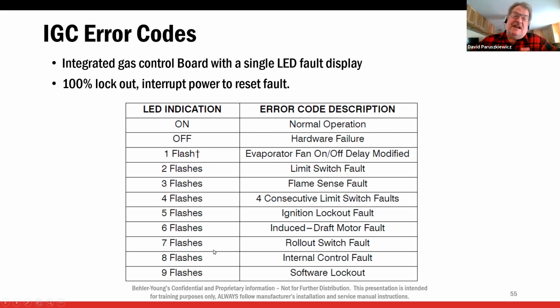So there are fault codes on the IGC. That little LED on there, on constant, is normal. Off means we probably lost our 24 volts or the fuse is blown. Single flash means that blower time has been altered, meaning it adjusted itself. So single flash is not a fault. It just means that the blower adjusted itself for heating, either on or off time. We'll talk about that. Two flashes, limit switch fault. Three flashes, flame sense fault. Four flashes, four consecutive limit switches, means the limit's tripped 4 times in the same heating cycle and it locked out. 5 flashes, ignition lockout. 6, inducer draft motor fault. 7, rollout switch fault. 8, internal control fault. 9, software lockout. So we'll talk about all these.